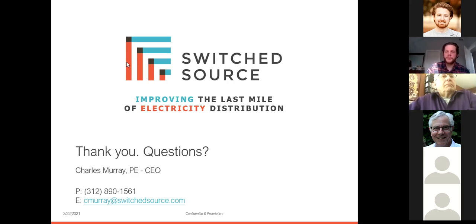The third piece is reliability. We wouldn't necessarily pick up load directly with our device—being grid forming on one side of it. But if load had to be switched onto one of our distribution circuits and it's now overloaded, we want to balance that out so the circuit is relieved a bit by an adjacent circuit. So it's a lot of balancing power. I'd love to say it's complex optimization, real optimal power flow, but it's not—it tends to be very basic algebra-type stuff.